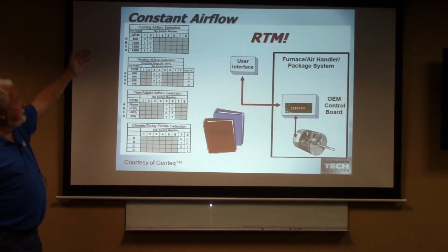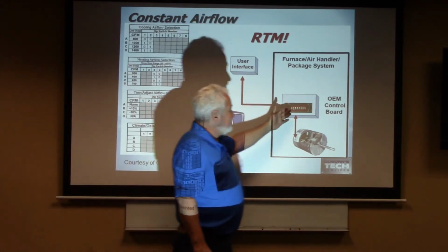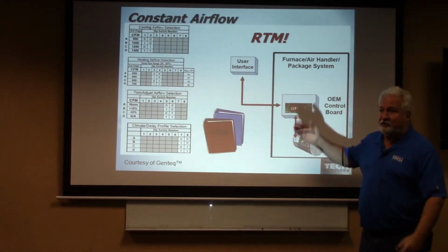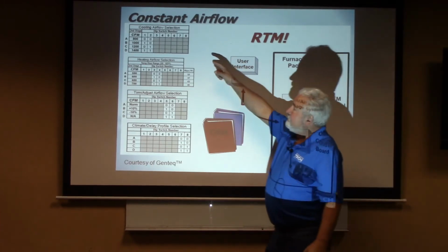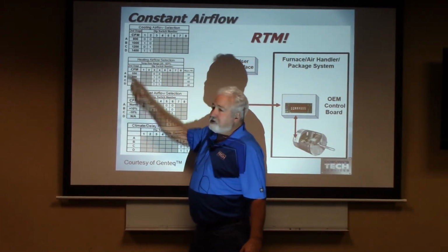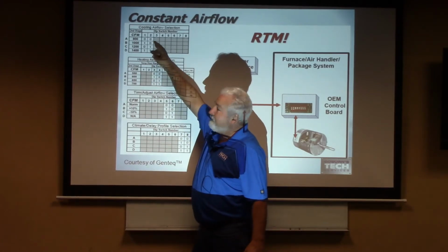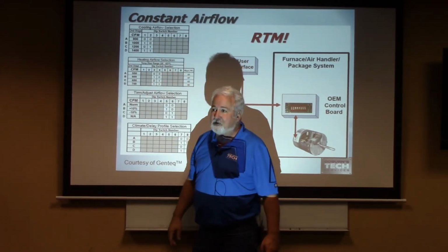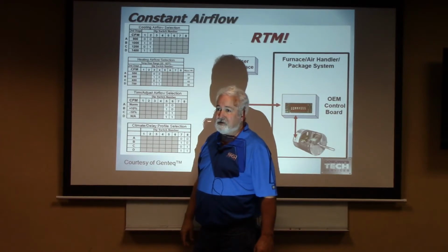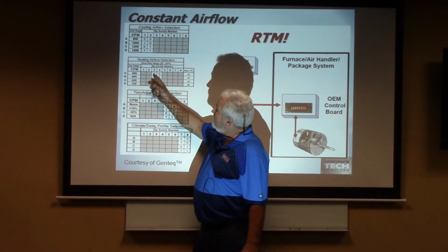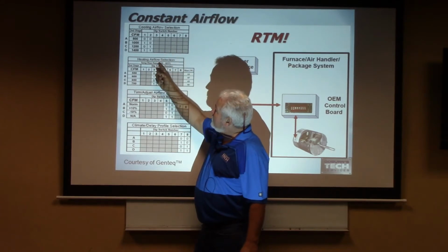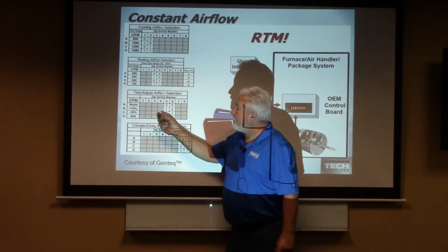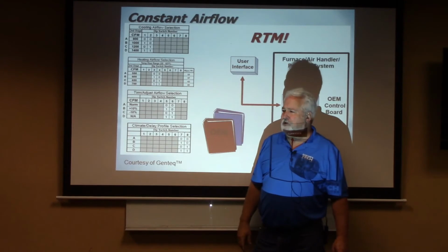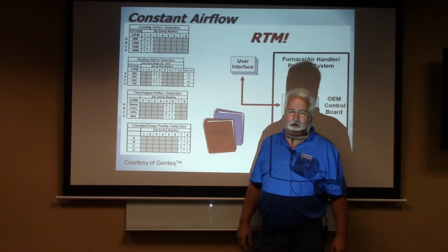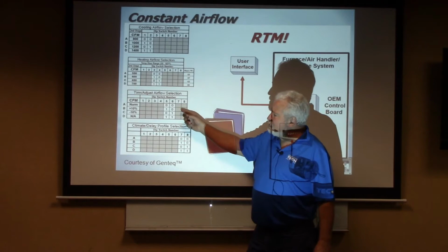Constant airflow motors. Guys, there's switches in here that you have to actually set. If it's an 800 to 1400 CFM motor, you have to set those. They don't come from the factory knowing what you guys are going to put it on. Does that make sense? You have to set that. You have to set your cooling airflow, your heating airflow, your trim, which says, okay, well, I don't want to have 400 CFM. I want to have 350 CFM per ton. So you're going to add your trim in there, either 10% up or 10% down.